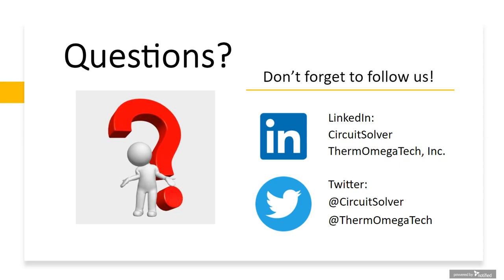And then let's see, the next question. Looking at your sketch for the two hot water system, I noticed what appeared to be a slight deviation from the single hot water system, and that there was no provision for making sure everything was set up for thermal disinfection of a given branch before the 160 plus water flowed through it. That's a really good observation. That's an oversight on my part.